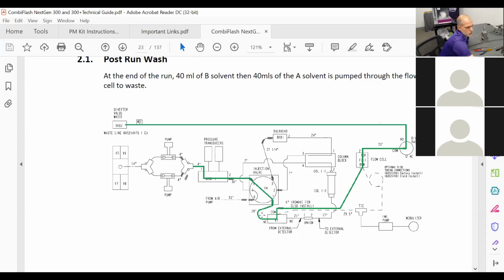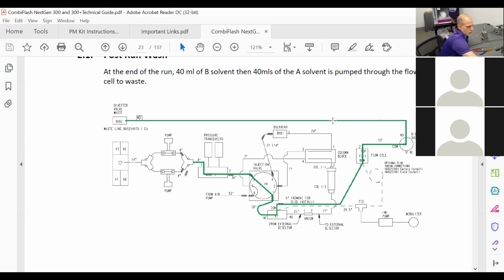Okay, so it's going through, and since this is a post-run wash, it's going through the injection valve, through that three-way valve, and then it's going right through the flow cell, through the diverter valve to waste. So it's cleaning off all this line. It's cleaning off the flow cell. It's cleaning out the diverter valve. I shouldn't say cleaning, that's bad terminology. It's flushing it, okay? So that you don't have any remnants of possible sample. It's kind of pushing through any solvent that may be lingering as well. Moving on.